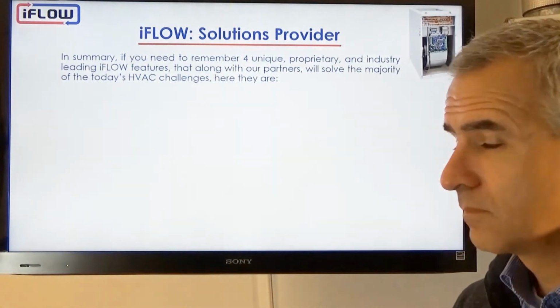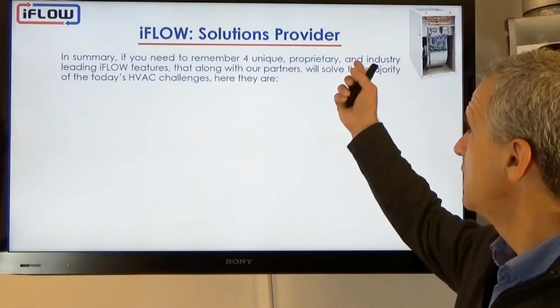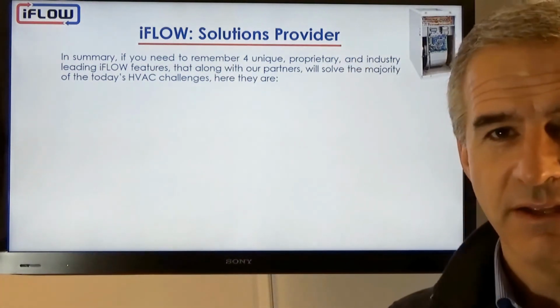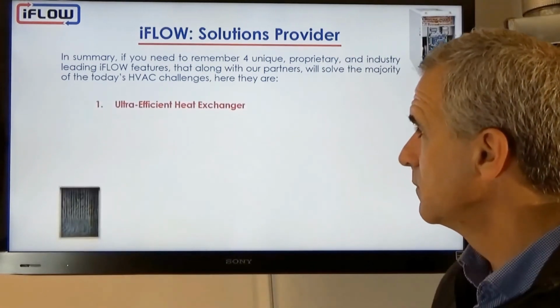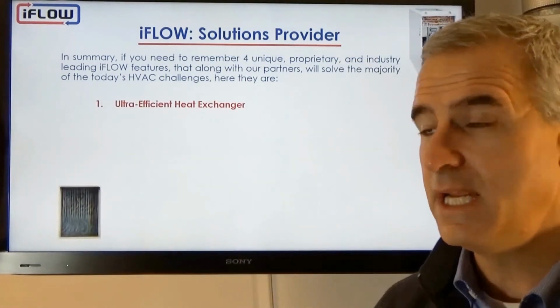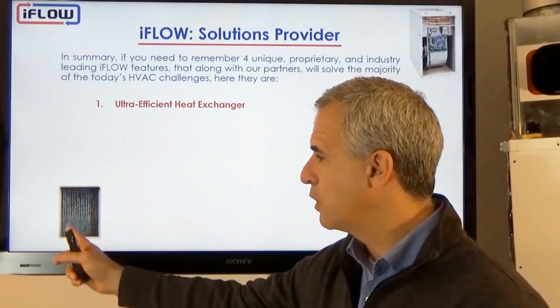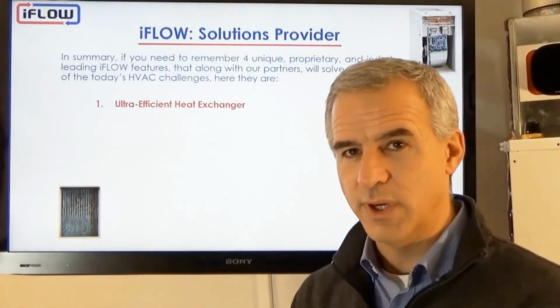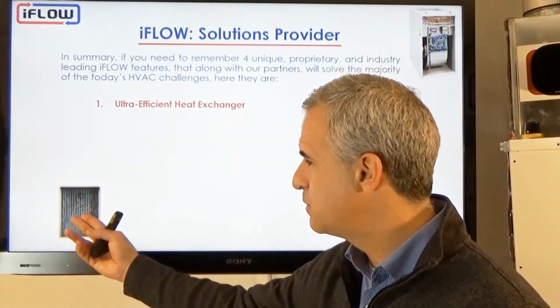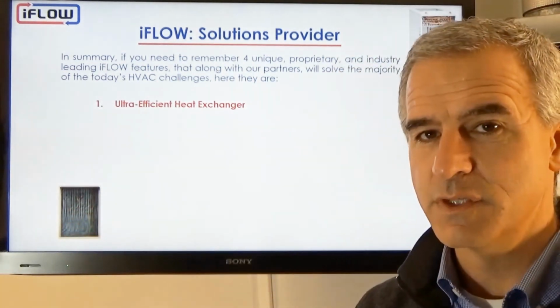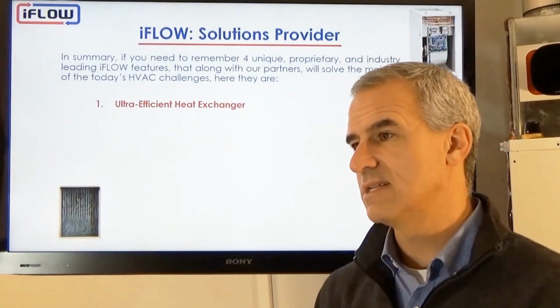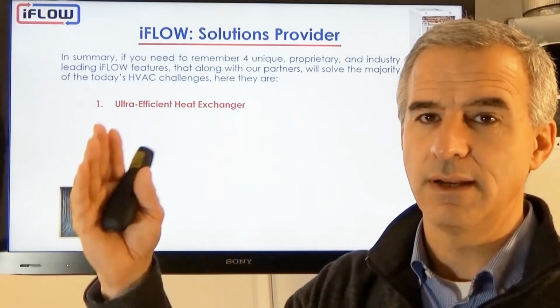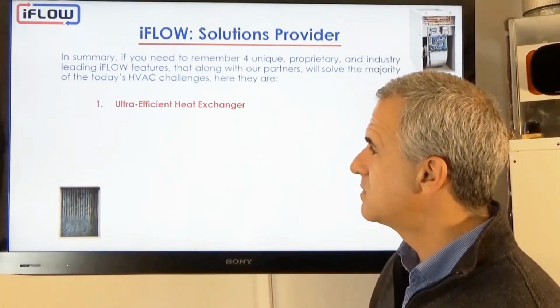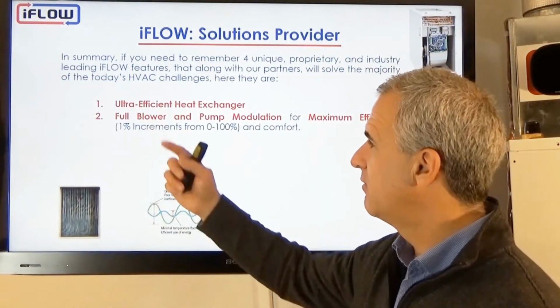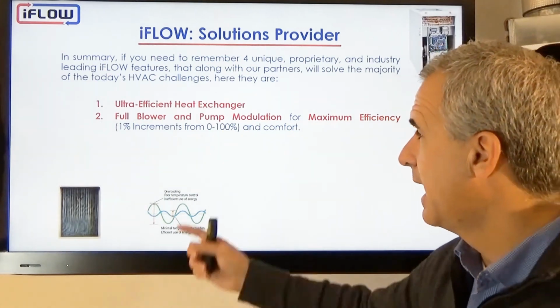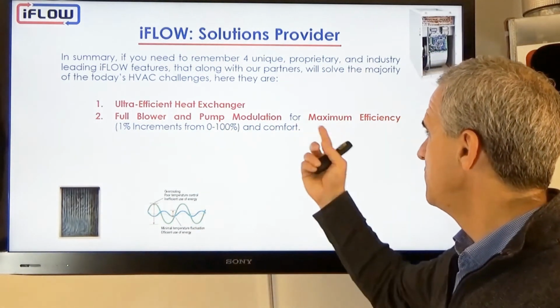So in summary, if you need to remember 4 unique, proprietary and industry-leading features. Number 1, iFLOW has an ultra-efficient heat exchanger. So again, our proprietary water pathway design combined with the high-density fin spacing and the special materials coating gives us premium efficiency. In most of the testing we've done, we're at 95% and higher with the various heat sources that we tested with.